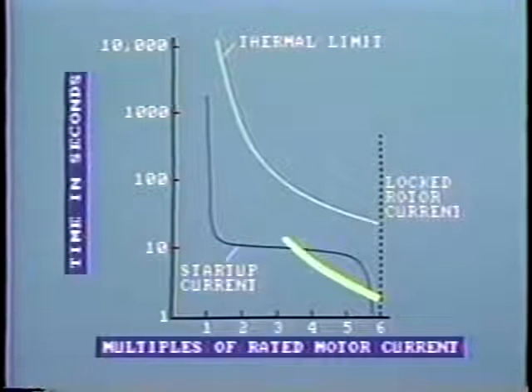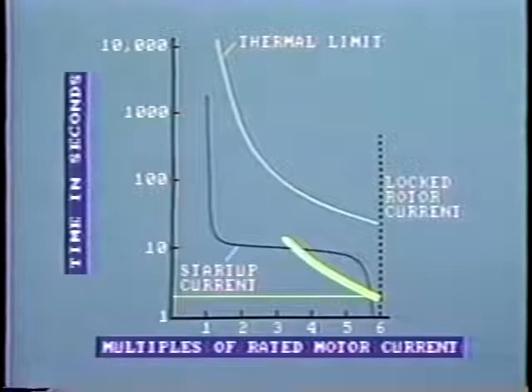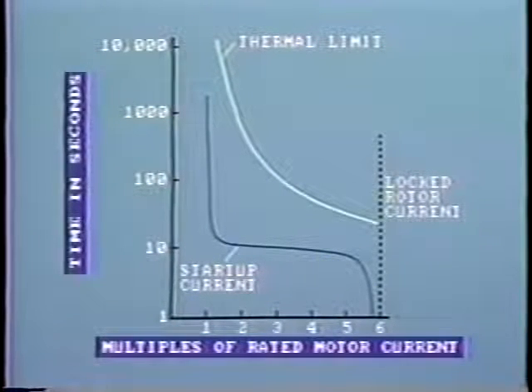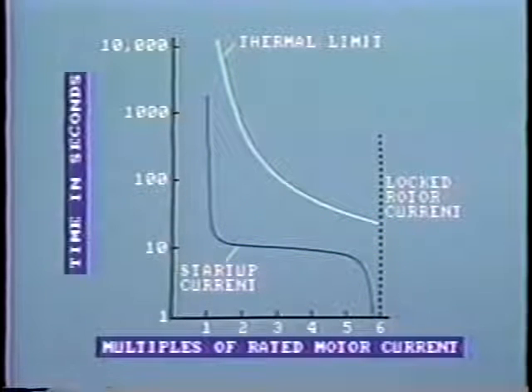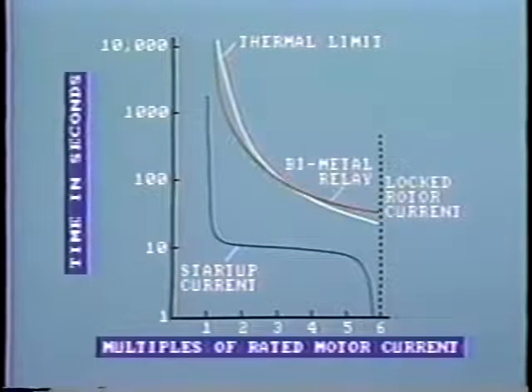Now, if the thermal relay was set to trip, say, in this area, we would not be able to start the motor. With just under 6 times rated current, the relay would trip in less than 2 seconds. So the thermal relay curve has to be set within this area here, between the thermal limit curve and the startup curve. In practice, we try to adjust the relay so that its tripping curve is quite close to the heating curve, like this, so as to prevent inadvertent tripping.